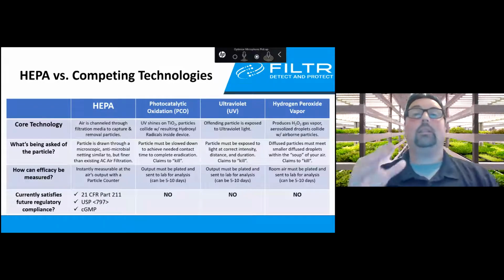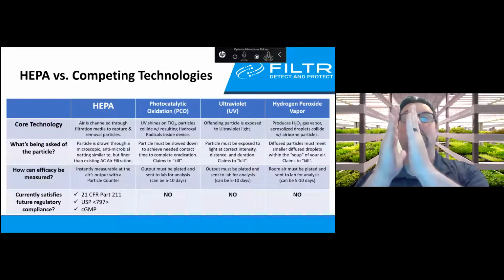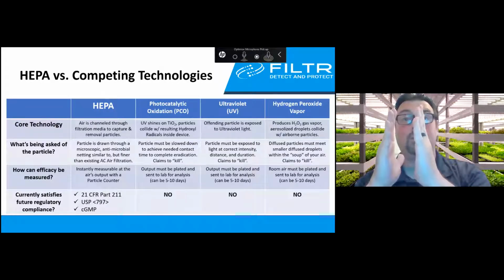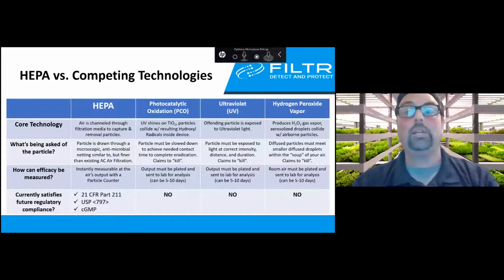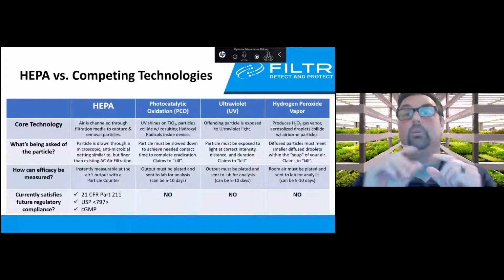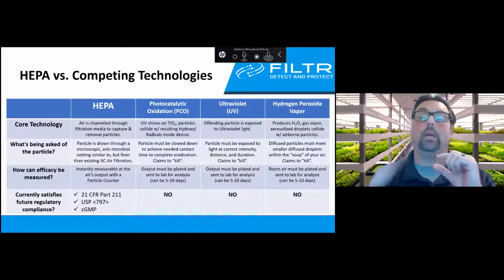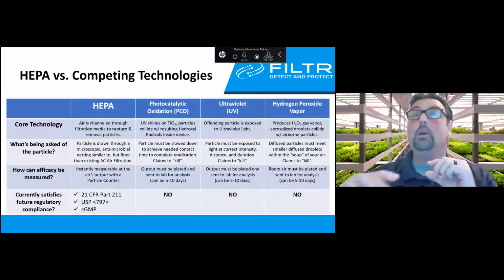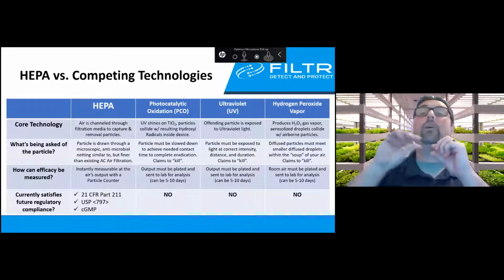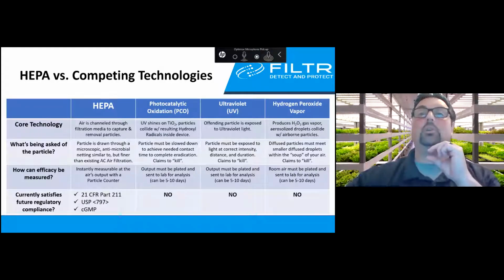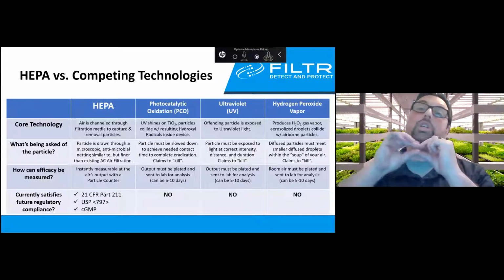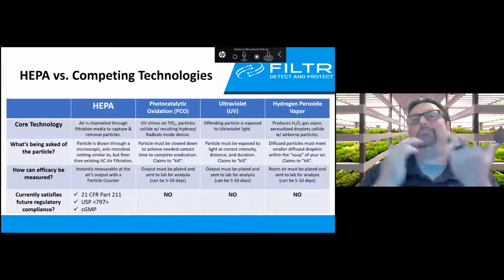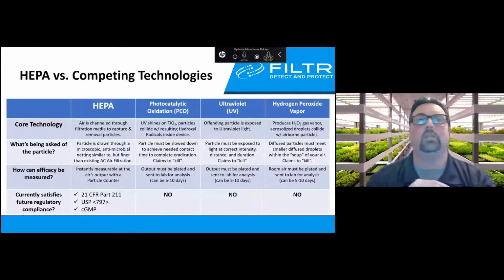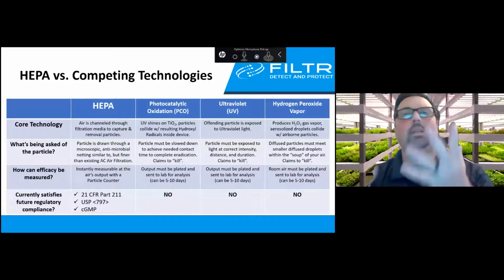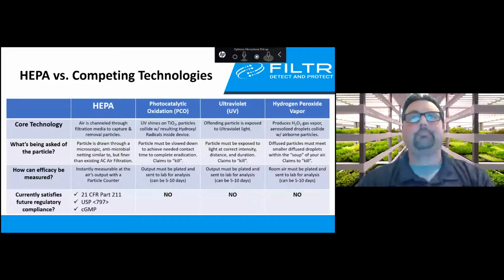But with a UV light, the light has to be at a very specific distance and held for a very specific amount of time. For example, it takes 30 seconds to kill COVID under UV light. So if you were to try to put UV lights in your air conditioning system in order to maintain that contact time, you would need 500 feet of straight air duct with a UV light in it in order to achieve that 30 seconds at like your average HVAC system. So it's not really wildly efficient.